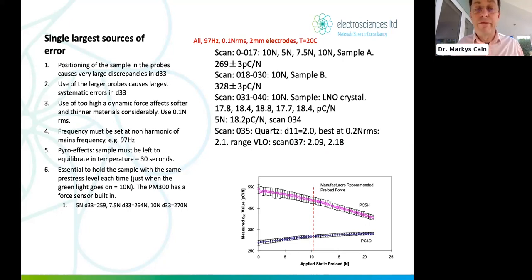Use of too high a dynamic force. We apply a static preload, maybe a Newton, maybe 2 or 3 Newtons, to hold it in place. That's important. But also the dynamic force, the small oscillatory force we use to excite it piezoelectrically, which we then use to measure the piezo charge response. That's important.